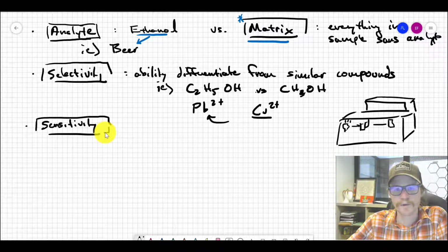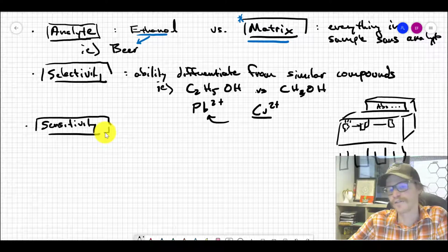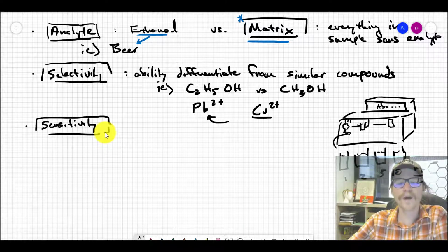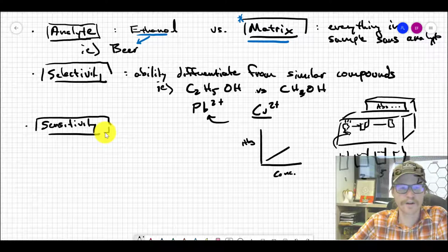some absorbance here, right? And when you're doing that calibration, you're going to run a bunch of different standards of differing concentrations. Maybe you run it at 1, 2, 5, and 10 milligrams per liter, each one being progressively darker in color, and you'd run them on your tool right there. When you do this, you generate a calibration curve, right, where you have absorbance versus the concentration of whatever that dye is, that thing you're trying to measure, and hopefully we get a nice straight line.